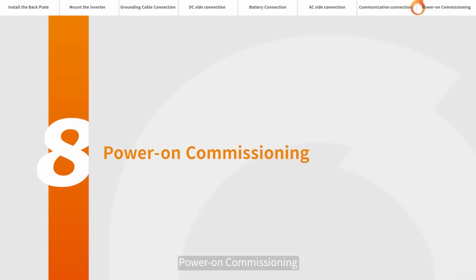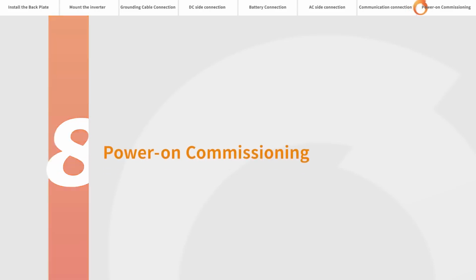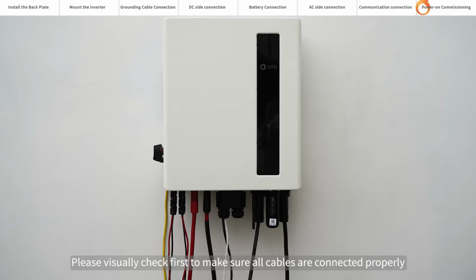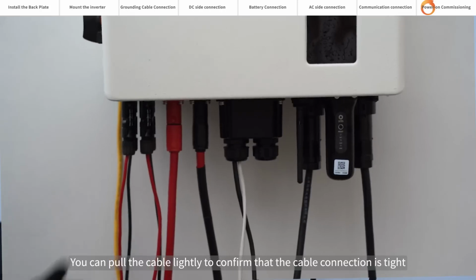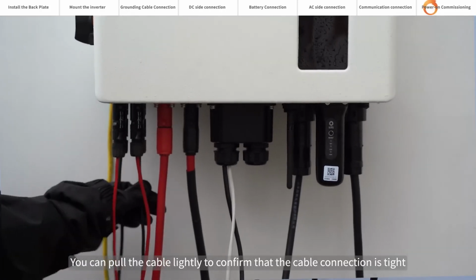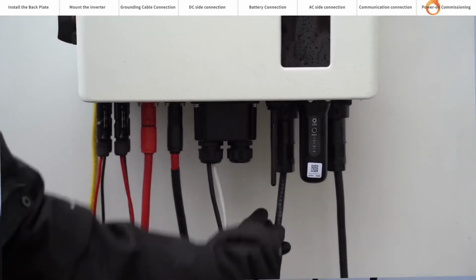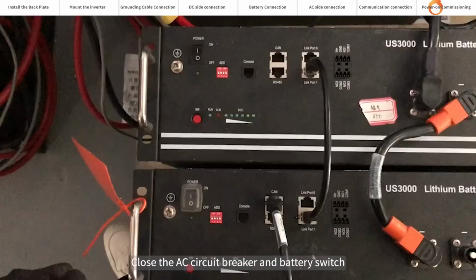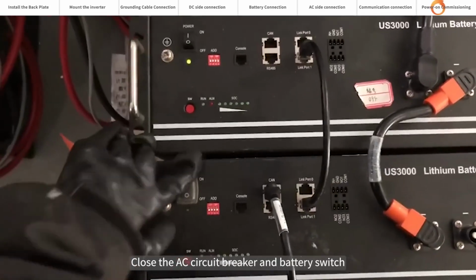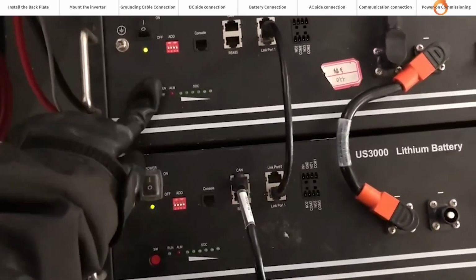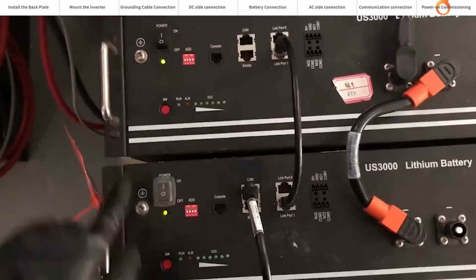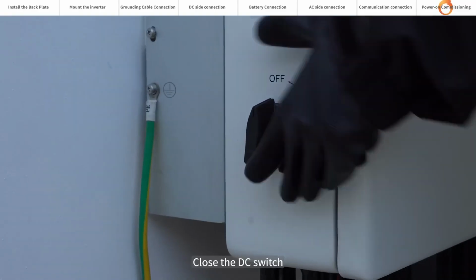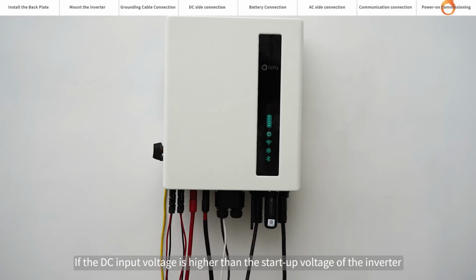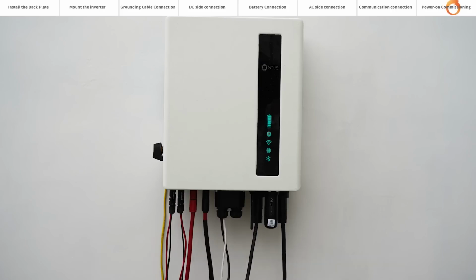Power on commissioning. Please visually check first to make sure all cables are connected properly. You can pull the cable lightly to confirm that the cable connection is tight. Close the AC circuit breaker and battery switch. Close the DC switch.